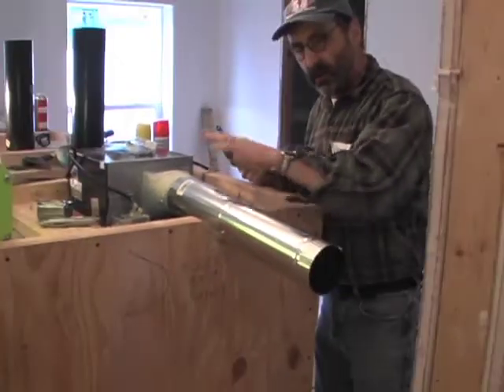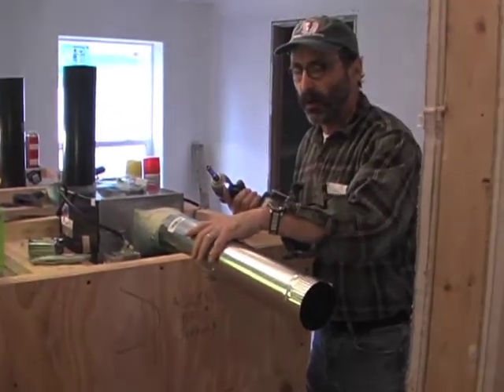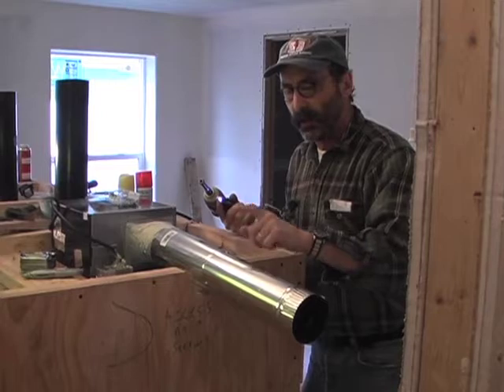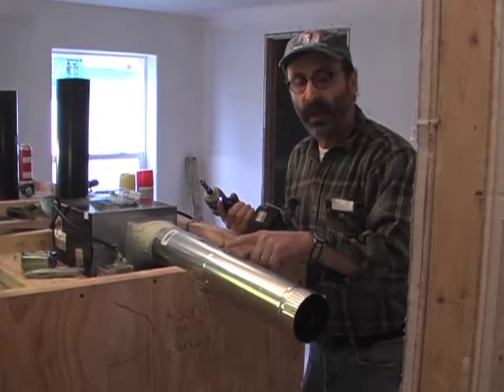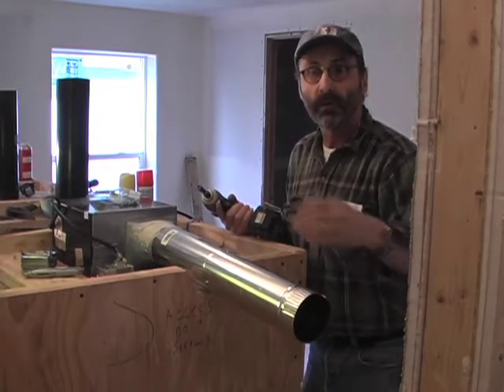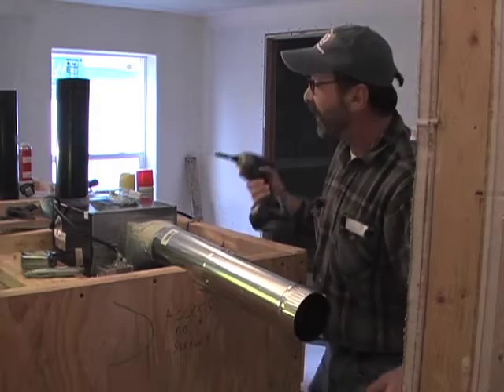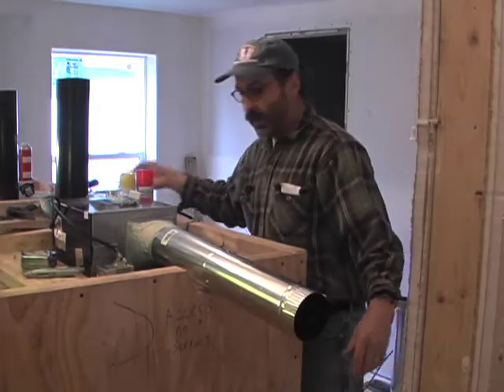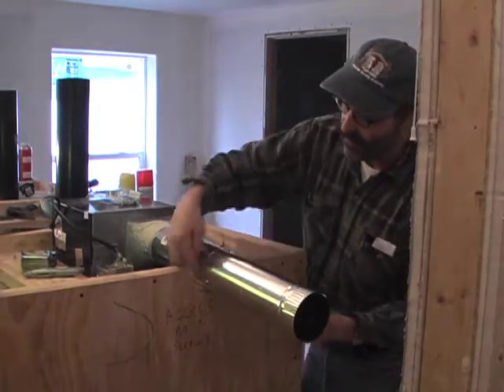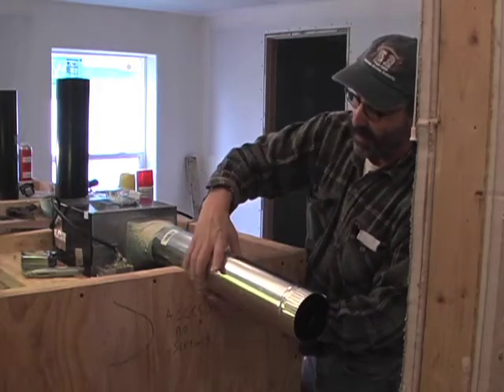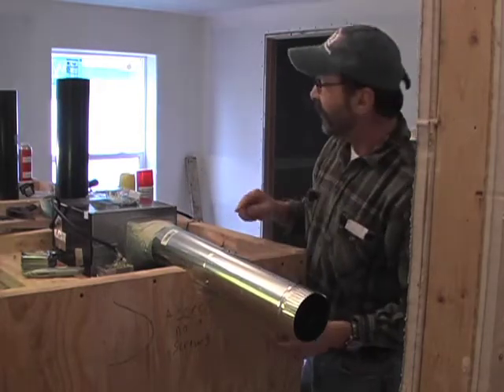As you run ductwork through an unconditioned space, depending on whether you're going to insulate the ductwork or not, consider the likelihood of getting condensation within the ductwork. Having it slope downward so that any moisture within will drain to the outside is always a good idea. Now we need to seal the butt connection and the longitudinal seam.